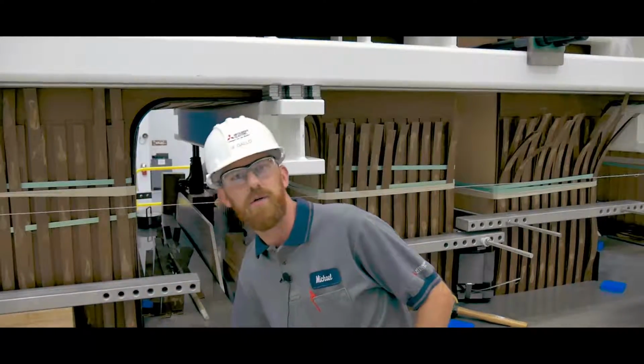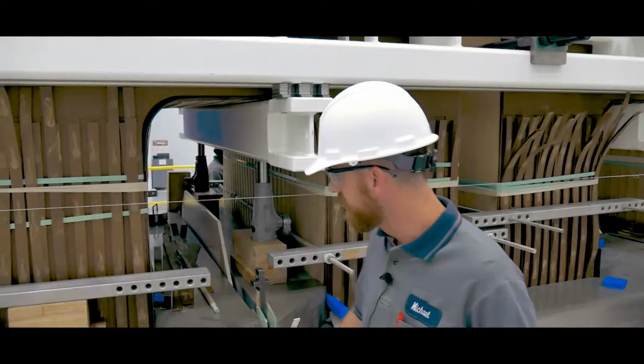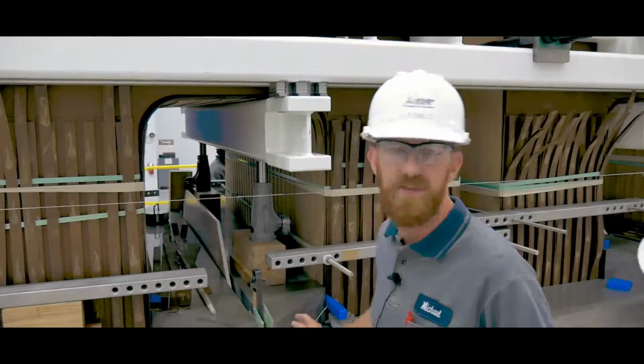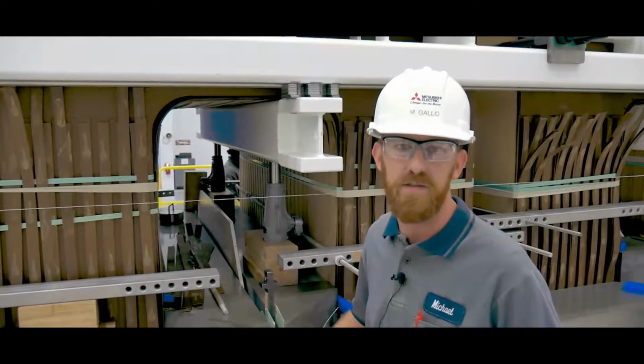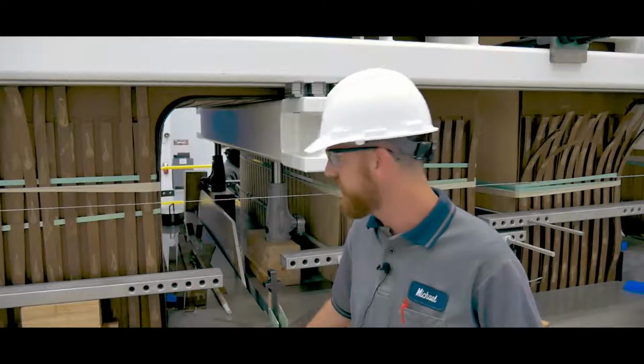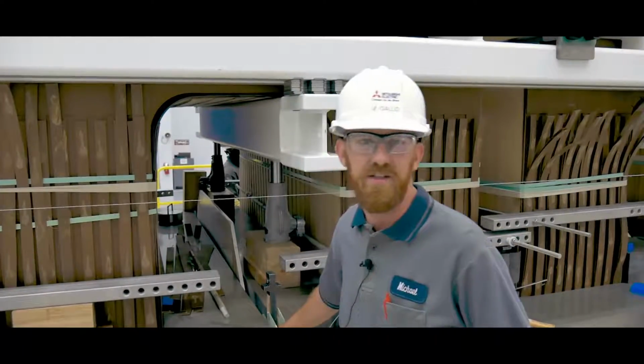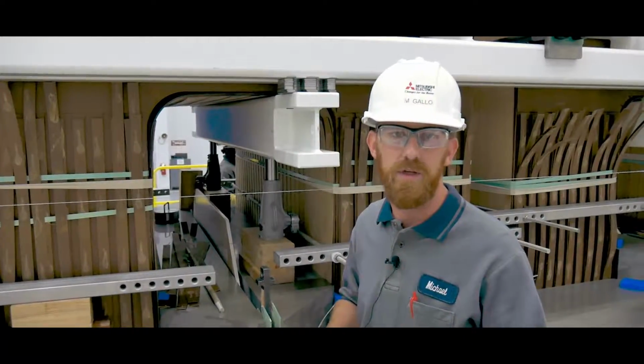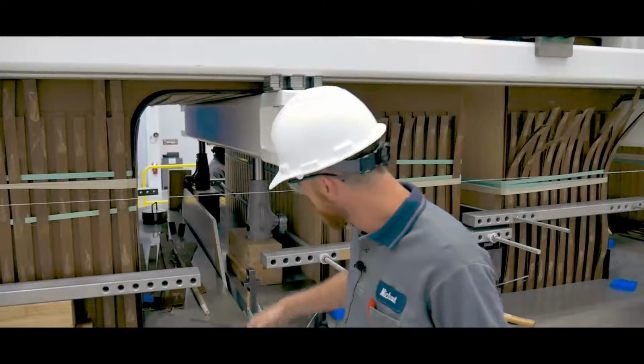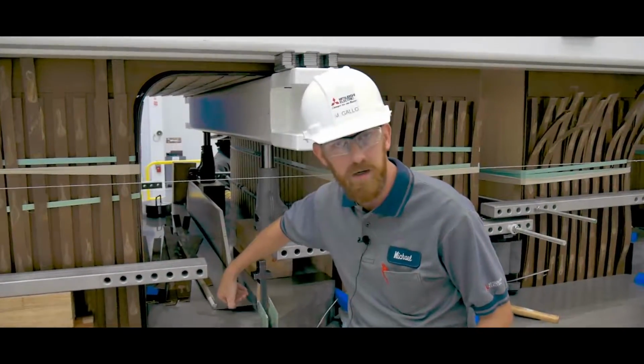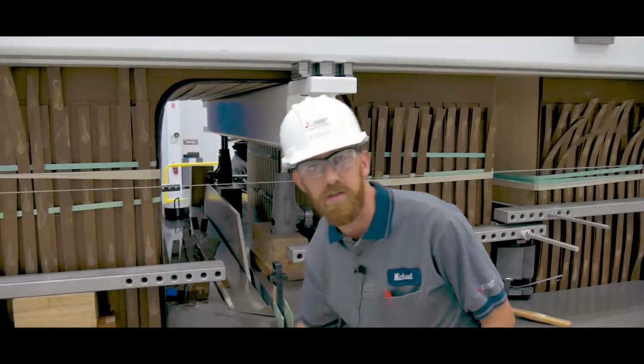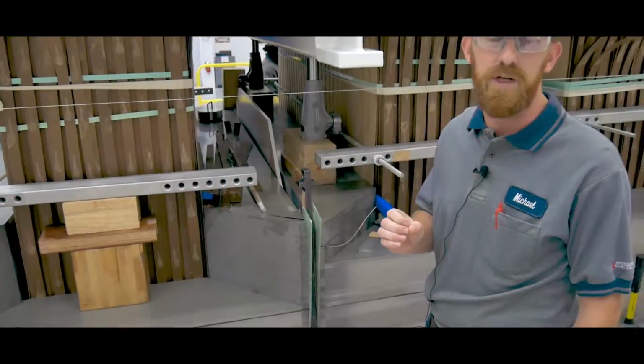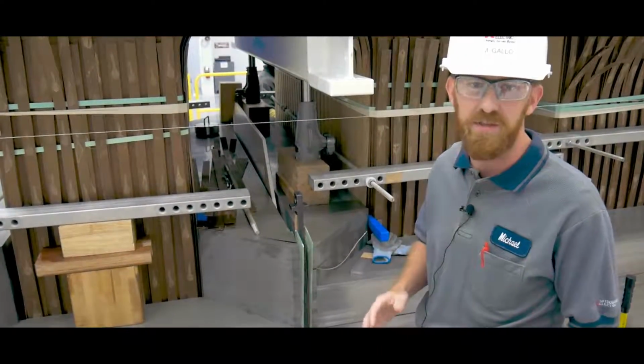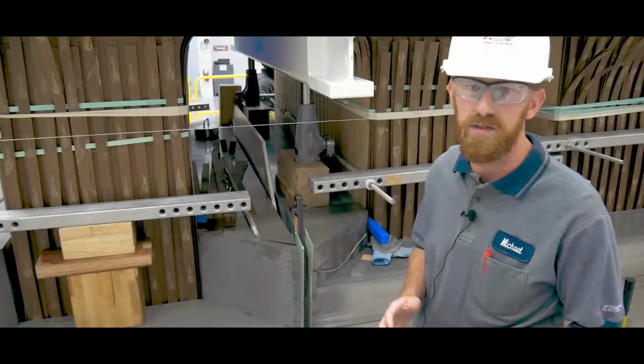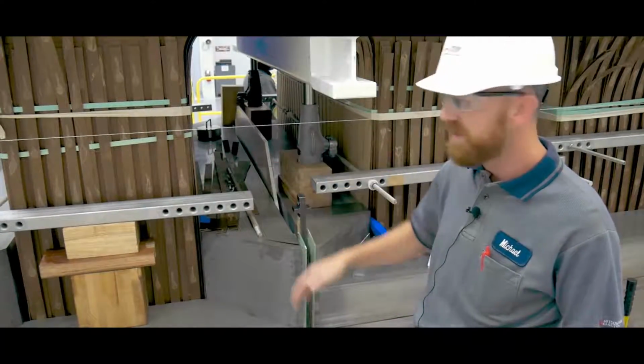Then the yoke steel will be inserted by hand. With this particular unit, a three-phase unit, there are hundreds of thousands of sheets of steel. We have to maintain a 2 millimeter joint gap from the yoke core to the leg core. This section will be jointed to that section, and our tolerance is 0 to 2 millimeters. Our job is to specifically maintain that tolerance from the bottom to the top.